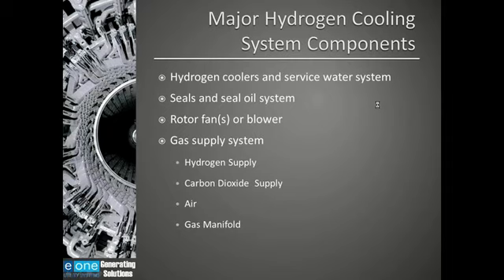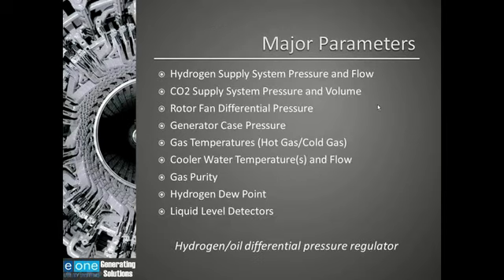This typically is your hot gas and cold gas temperature, and I won't be discussing other temperatures such as a stator temperature. They may have some end winding temperatures. We'll discuss the cooling water temperatures and flows. In detail, we will discuss gas purity, measuring gas purity, not only hydrogen but the purge gases. We will discuss the hydrogen dew point monitoring and liquid level detectors.